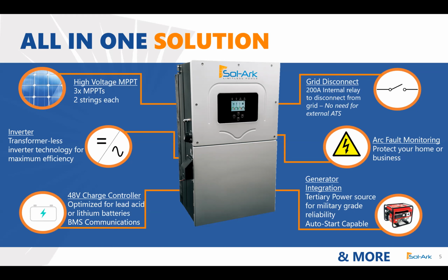And the fantastic thing about the Sol-Ark 15K is we have a 200 amp bypass. So that means you can actually land the backup portion of the inverter onto the top lugs of a 200 amp service panel. And if we can't provide the power and you're grid tied, we're going to pull that power from the grid and provide it to the loads. And the second we lose that grid connection, we have an internal relay that'll disconnect within 5 milliseconds. That's UPS grade speed. It'll disconnect and isolate us from the grid and continue to provide power to that load output.